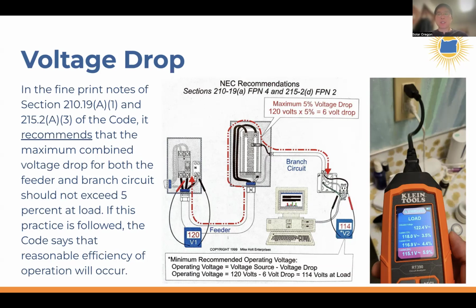Outlets near the end of that branch circuit could have significant voltage drops, and an electrician with proper testing equipment can measure the voltage drop when you plug something in and put a load on that receptacle. The National Electric Code recommends voltage drop should not exceed 5%, and I've seen homes where it's like 17%. If you plug in something that uses more than a few watts, like a laptop or a cell phone, or something like a refrigerator, on a plug that has a 17% voltage drop, you might run into significant problems.